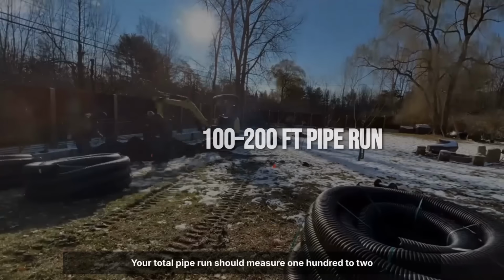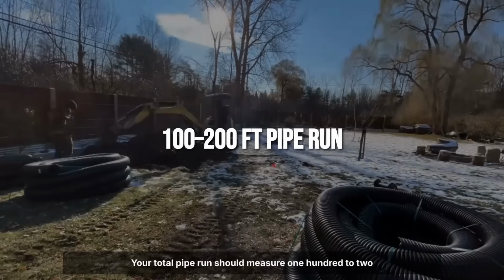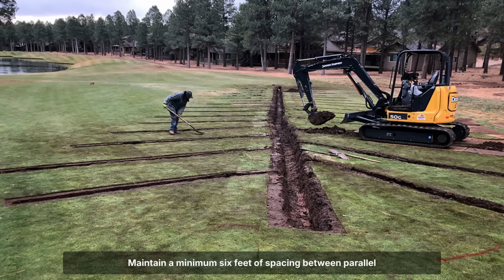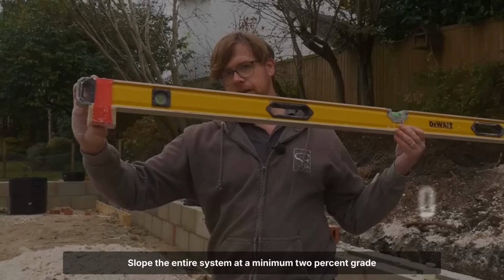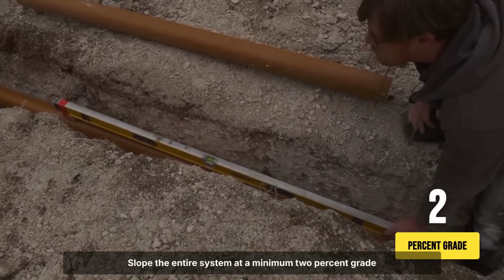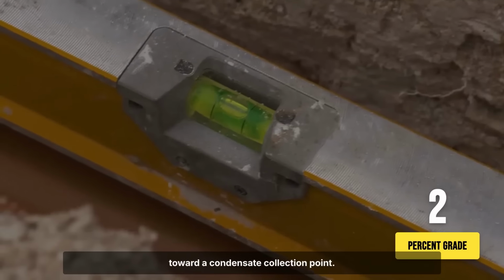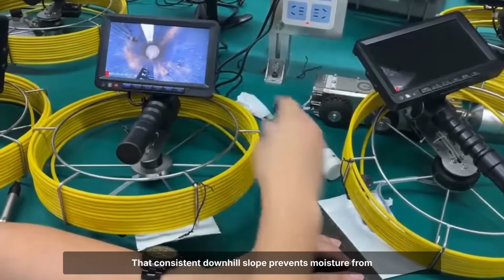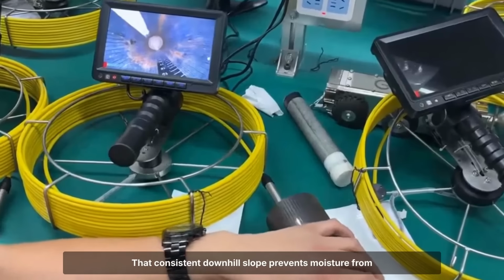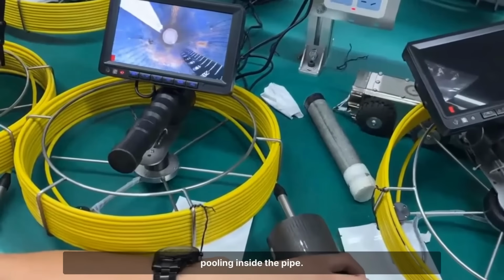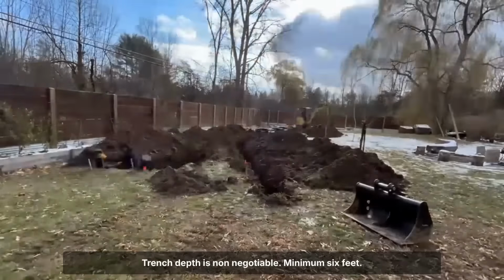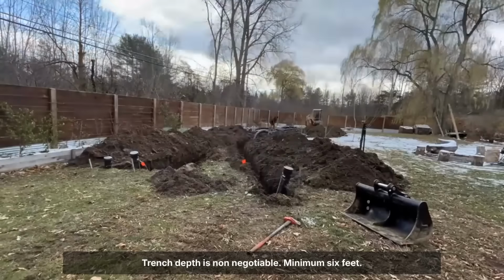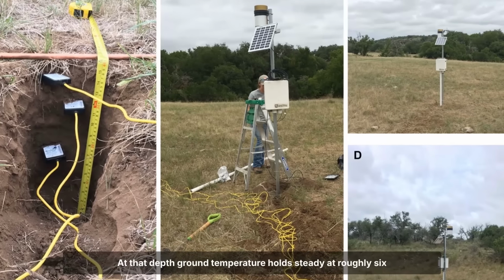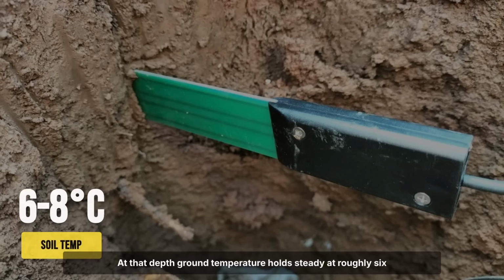Your total pipe run should measure 100 to 200 feet. Maintain a minimum 6 feet of spacing between parallel runs. Slope the entire system at a minimum 2% grade toward a condensate collection point. That consistent downhill slope prevents moisture from pooling inside the pipe. Trench depth is non-negotiable. Minimum 6 feet. At that depth, ground temperature holds steady at roughly 6 to 8 degrees Celsius year-round.